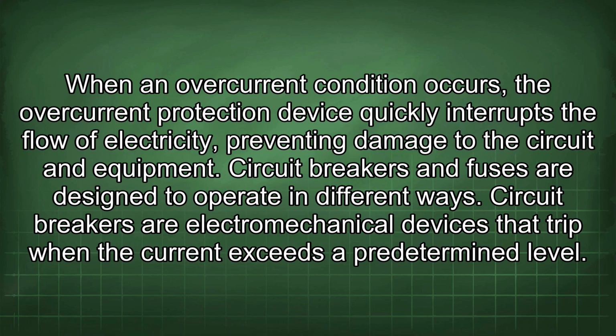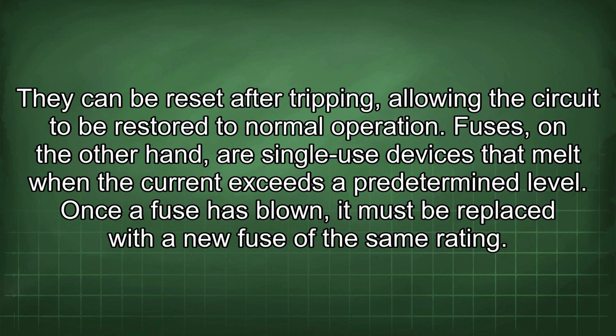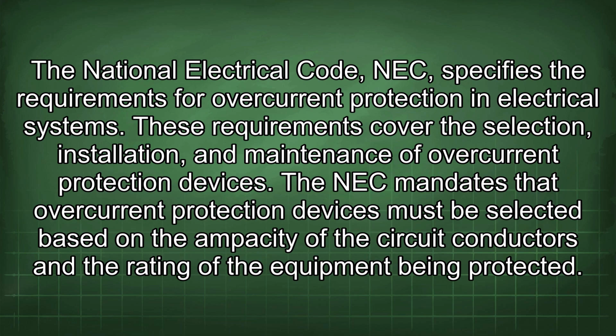Circuit breakers and fuses are designed to operate in different ways. Circuit breakers are electromechanical devices that trip when the current exceeds a predetermined level. They can be reset after tripping, allowing the circuit to be restored to normal operation. Fuses, on the other hand, are single-use devices that melt when the current exceeds a predetermined level. Once a fuse has blown, it must be replaced with a new fuse of the same rating. The National Electrical Code (NEC) specifies the requirements for overcurrent protection in electrical systems.